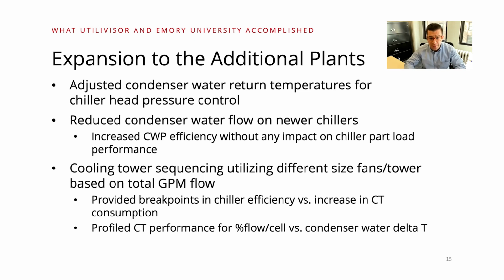With the new machines that were installed, they also had drives installed on the condenser water pumps, and we were able to show, still within manufacturer specs, that we were able to save on auxiliary efficiency by lowering that flow slightly without any impact on chiller performance. And again, from another auxiliary standpoint, one of the plants has different cooling tower fan sizes. So we were actually able to show, with a little bit more surface area, you were actually better off running a larger fan that had a larger horsepower, because the heat transfer was better, and the fan didn't work as hard from the fan affinity loss.